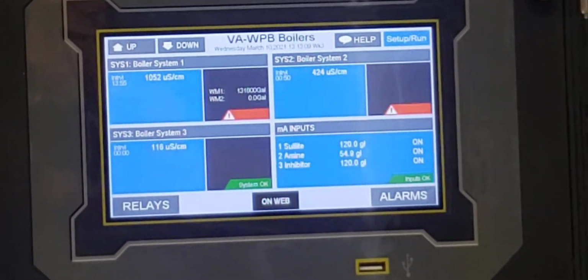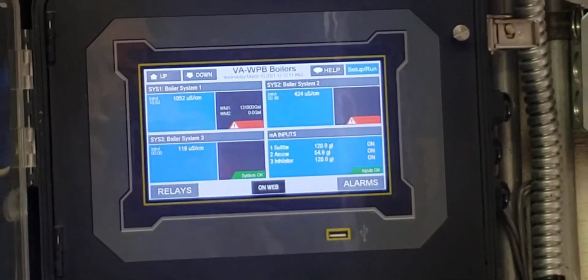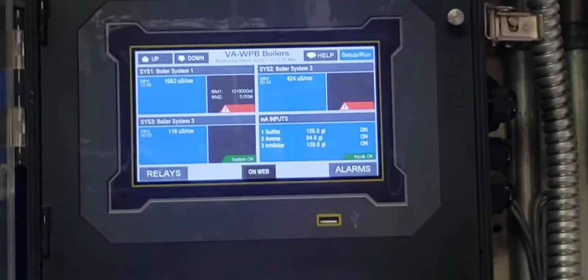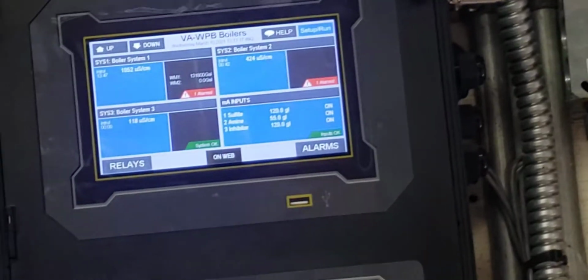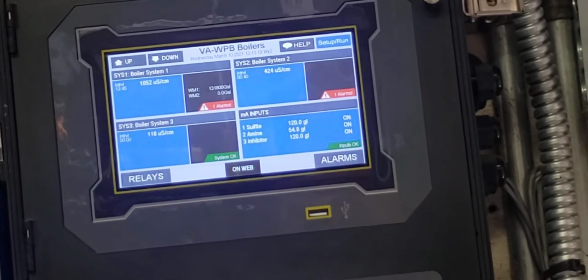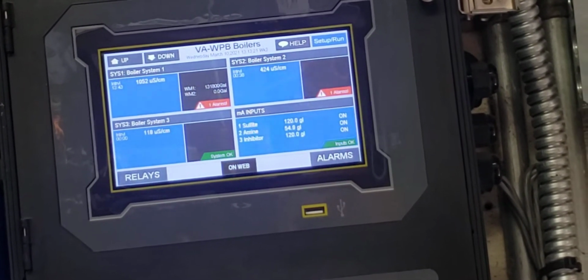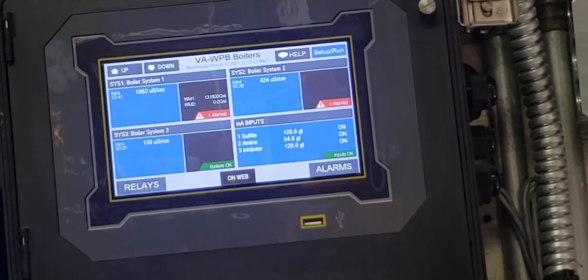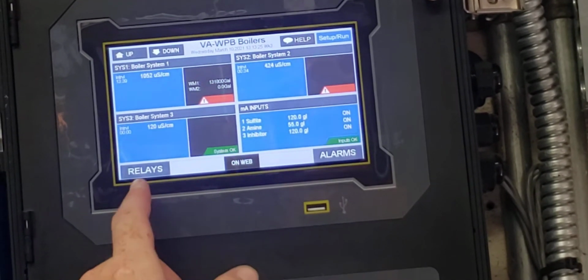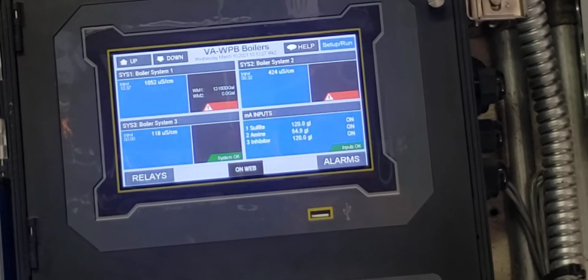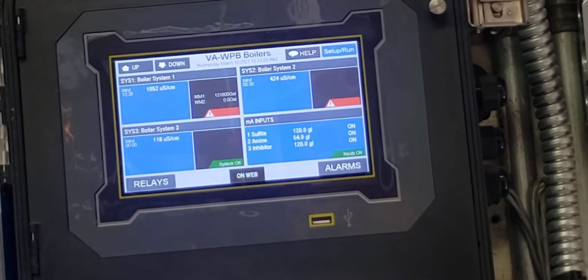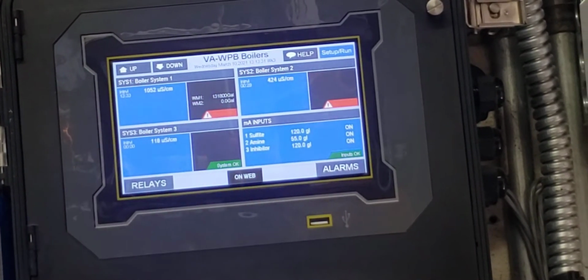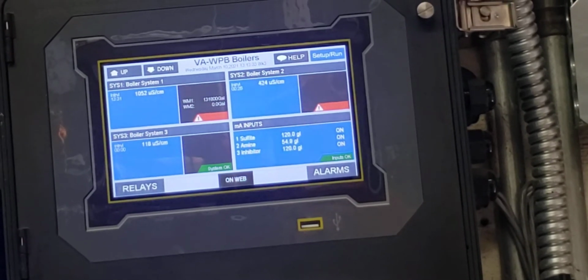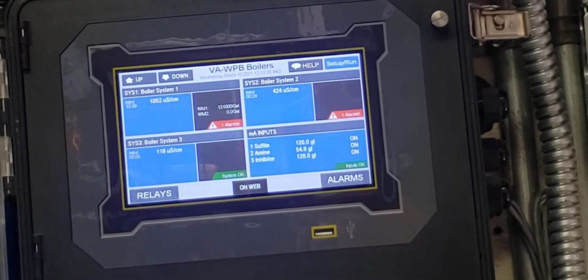Again, it doesn't have to be perfect. I'm looking for, hey, you got 3,000, this says 1,000, we got a problem, right? Or the big problem is if it's not blowing down and it should be. If it's high, then we definitely want to make sure that we change it. So now we know that we opened the valve, or it just did an interval, so we know that it has a fresh sample on the probe on top.